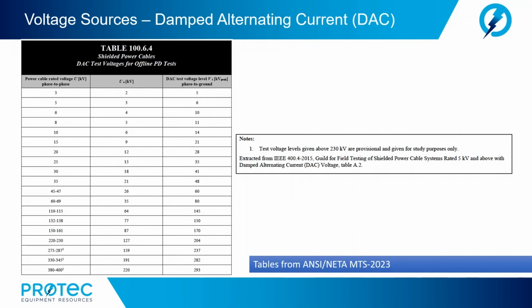All right, going back to our NETA standards, we do see that NETA has included damped alternating current, or DAC, into the NETA guides. We see this in table 100.6.4, shielded power cables, DAC test voltages for offline PD tests. So here, NETA does not necessarily look at using DAC as a withstand test and giving reference to how many excitations or how many pulses would be required to perform an effective withstand test. But we do see that DAC is now included in the NETA guides, particularly in the area of conducting offline partial discharge tests.